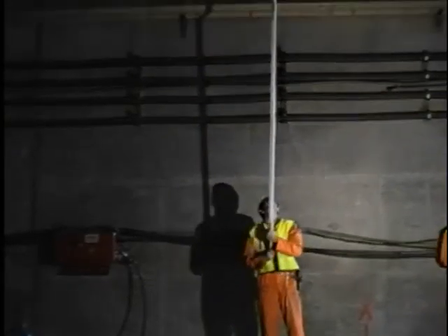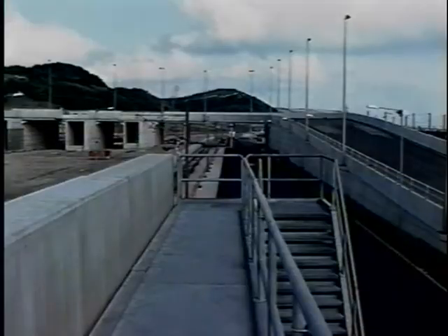So going back to the earthing again, these earthing straps, they're going to be with us throughout then. That'll always be the case that these cables need earthing down prior to anybody working on that section. Yes, that's got to be, because it's your protection, it's protection against anybody closing a breaker or residual or, you know, induced voltages within the system.